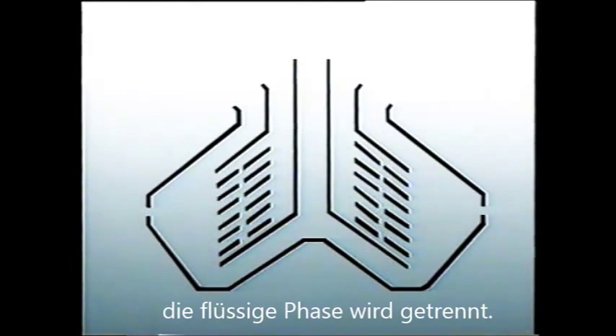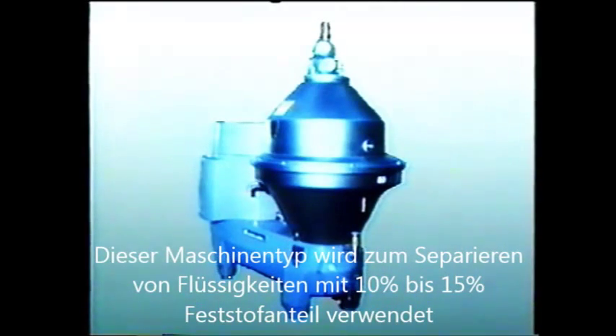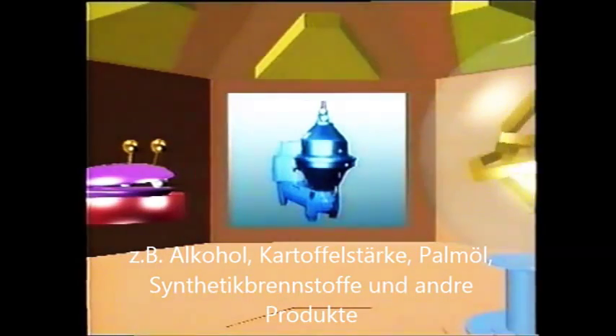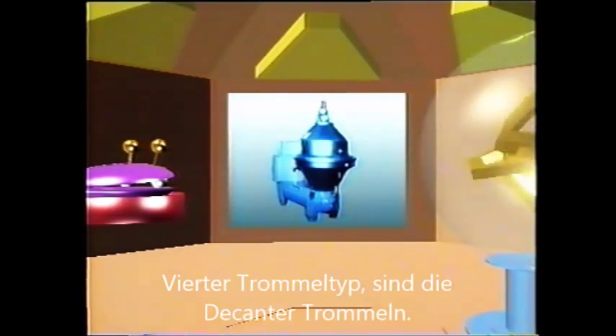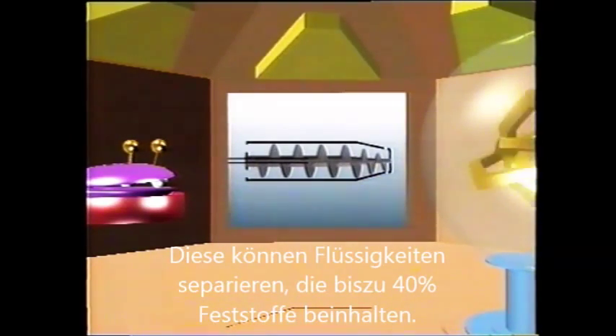This type of separator is used for suspensions that contain larger quantities of solids — between 10% and 15% — like yeast, alcohols, starch, palm oil, or synthetic fuels. A fourth type of separator, known as a decanter centrifuge, can handle liquids containing as much as 40% solids.